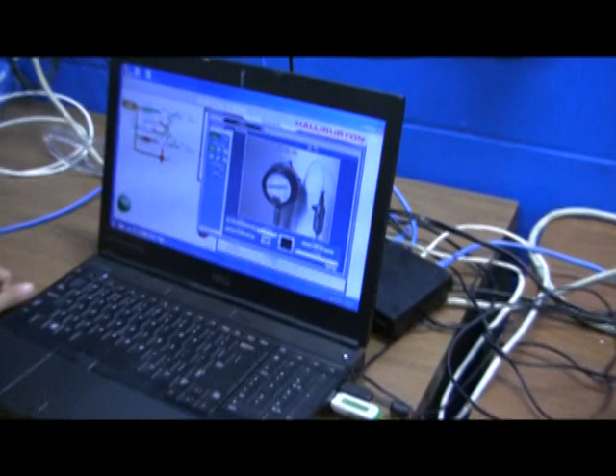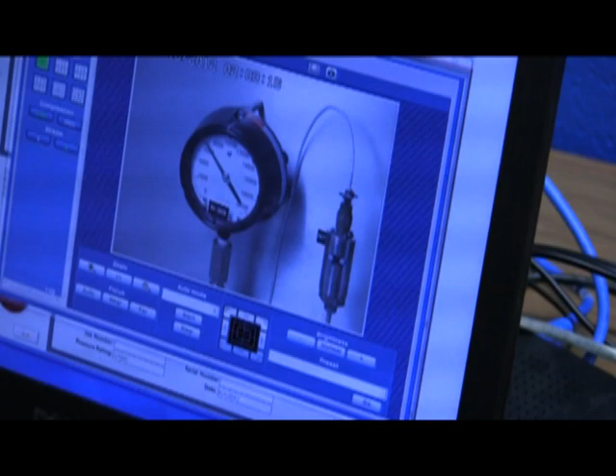We've got our manual analog gauge here and our digital transducers over here. We're going to ease up on the pump, give it a little more current, and you'll see the pressure build as current increases. We're trying to get it to around 15,000 or so, maybe between 15 and 20, then hold it. That's about 15.2, 15.3.